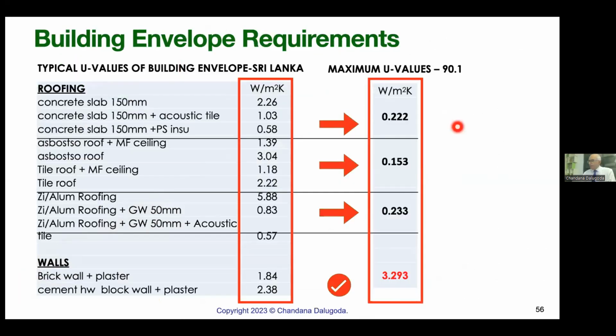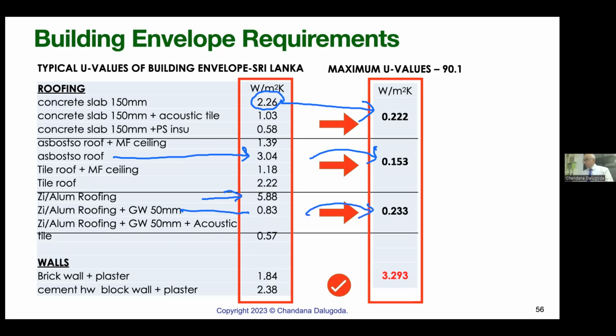Now there's a little comparison for you to understand U values. In Sri Lankan normal buildings that we use, say concrete slab 150 millimeter, U value is 2.26. If you want to convert this building to a green building or net zero building, you'll have to drop this to 0.22 with thermal insulation. Asbestos roof, normal asbestos roof, U value is 3 watt per square meter Kelvin. You'll have to drop it to 0.153. Zinc alum roofs, very hot, 5.88, but we use a glass wool 50 millimeters, so it is 0.83. But we'll have to drop it to 0.22. Brick walls, you don't need because that is very low compared to our standard requirement.